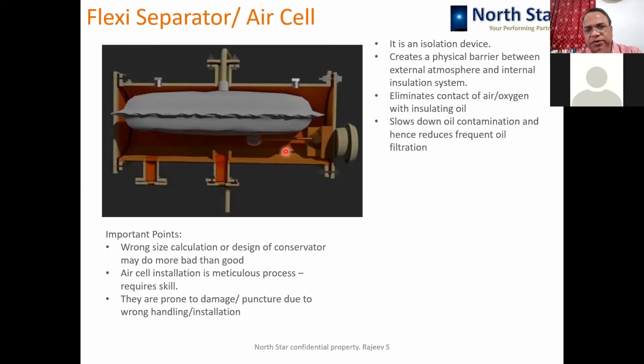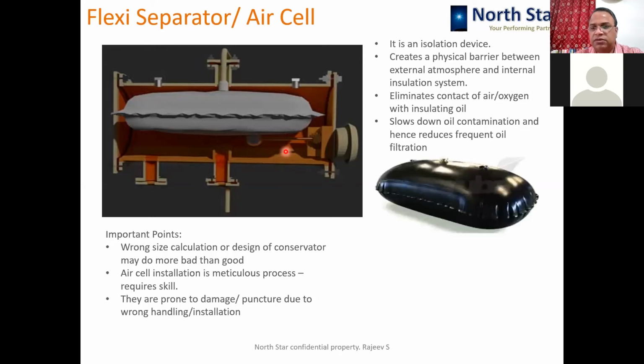Sometimes they get punctured because ultimately it is a rubber bag. So this rubber bag gets punctured. There is a big joint, and this joint sometimes gets opened. So it has its own problems. So you have to be careful about the air cell working condition. By looking at the indicator, you will know whether the oil level indication is correct. If it is not correct, then you can conclude that your air cell has some problem.